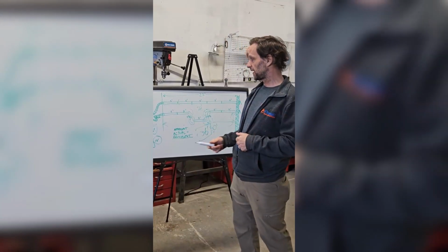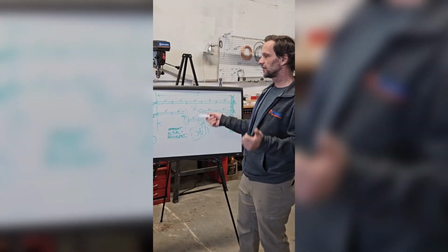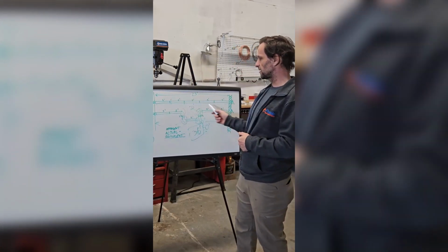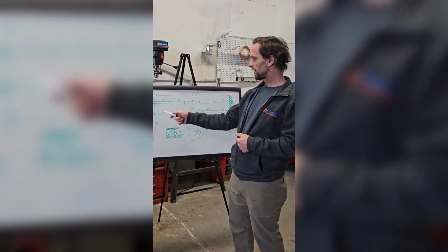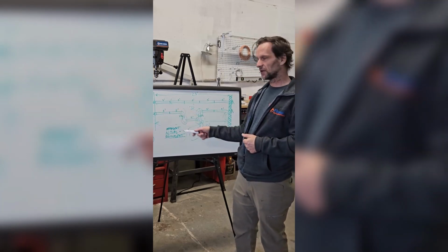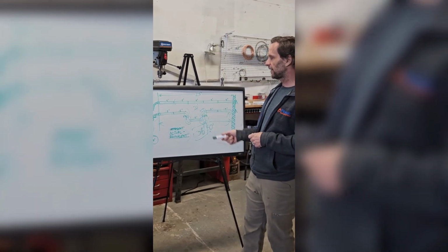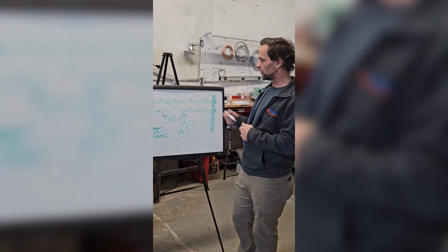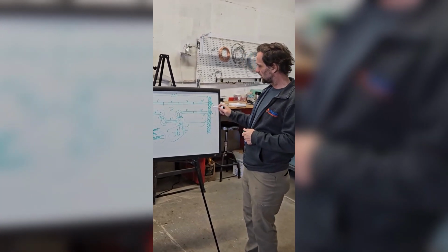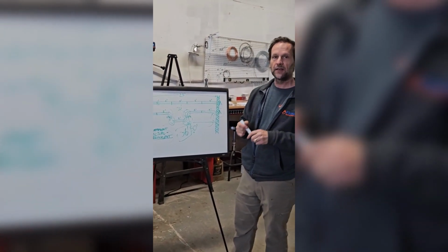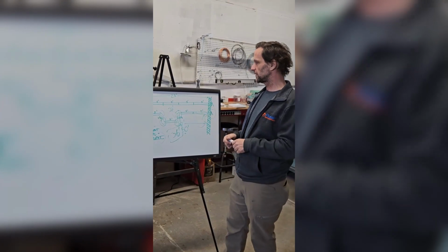The second point is make it as straight as possible. Again, not always possible, but if there is a possibility, even if it's a longer run, get the longer run and make it straight. It's going to have a shorter equivalent length than maybe a shorter run with a lot of fittings on. And the third point is, if you're already stuck with whatever you have, change individual fittings. Not just the fittings: change the vent, change the hose, change every single element that you can and replace it with a more efficient one.